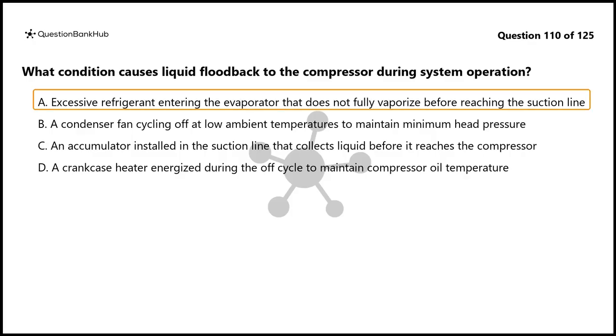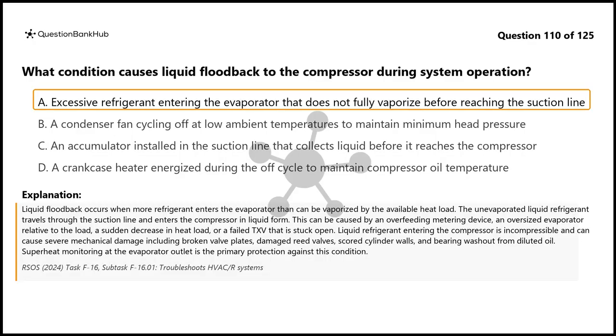The correct answer is A. Liquid floodback occurs when more refrigerant enters the evaporator than can be vaporized by the available heat load. The unevaporated liquid refrigerant travels through the suction line and enters the compressor in liquid form. This can be caused by an overfeeding metering device, an oversized evaporator relative to the load, a sudden decrease in heat load, or a failed TXV that is stuck open. Liquid refrigerant entering the compressor is incompressible and can cause severe mechanical damage including broken valve plates, damaged reed valves, scored cylinder walls, and bearing washout from diluted oil. Superheat monitoring at the evaporator outlet is the primary protection against this condition.